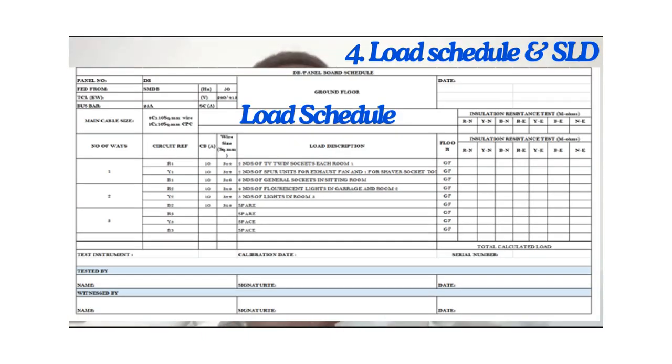And then as such, when we pull our wires, we should be able to provide labeling or identification labeling. A temporal marking is okay. Get a masking tape, put it there, and then write the circuit reference as per the drawing, so that while you are proceeding with the installation work, you might finish with the cable pulling, you want to now start doing continuity and megger tests, you should be able to identify different circuits that you pull. While you're carrying out your test, you know the different circuit which you are carrying out the test is important.